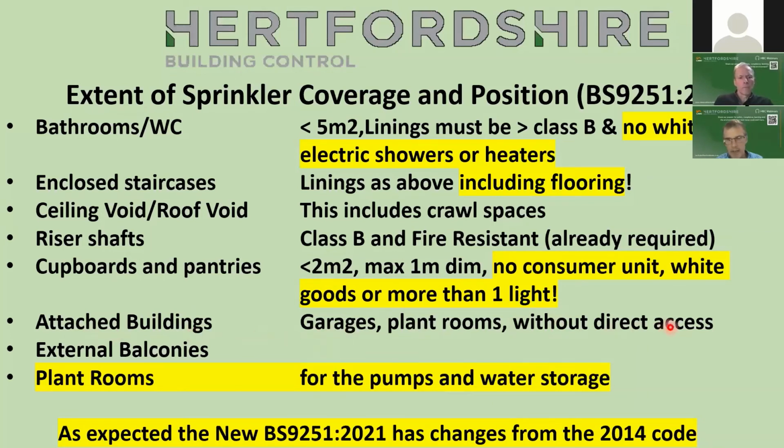Attached buildings haven't changed, so they're external. Plant rooms for the water pumps and the water storage now need to be sprinkled in accordance with 9251. So, like I said, what's to take away from this is the new 9251 has got changes and is different from the old code, and those are roughly the changes in relation to what's exempt for coverage.